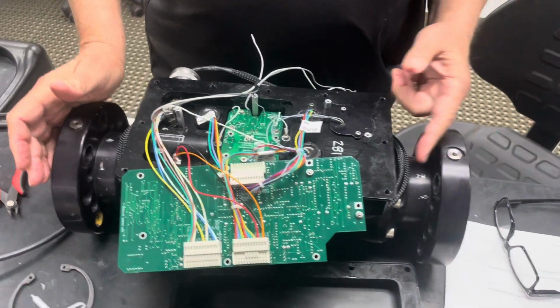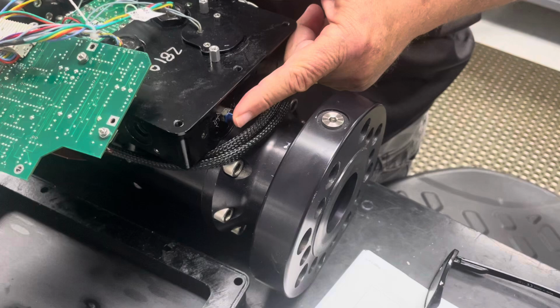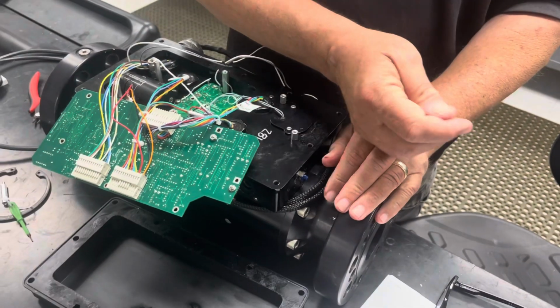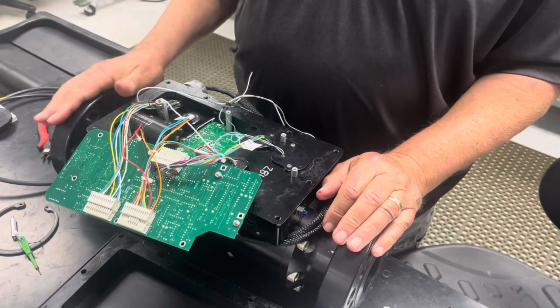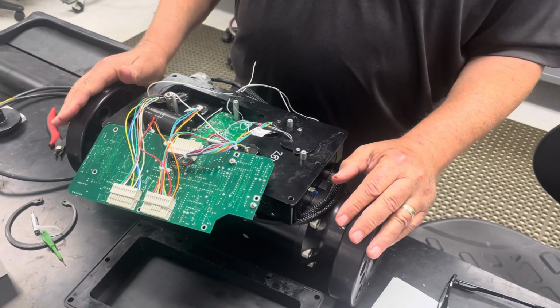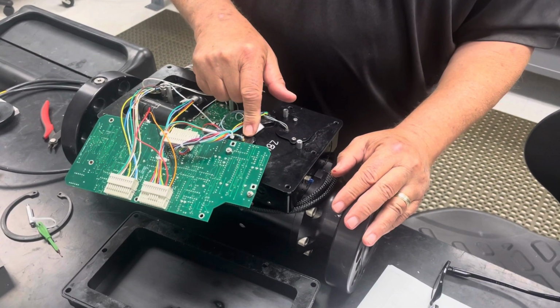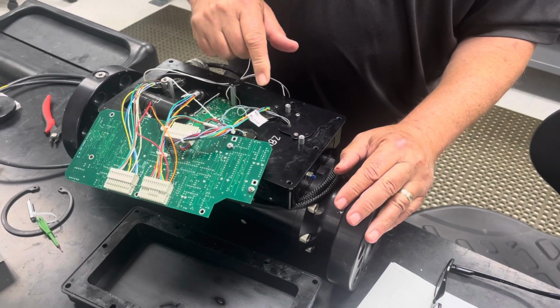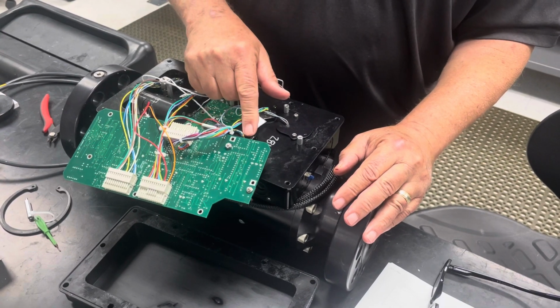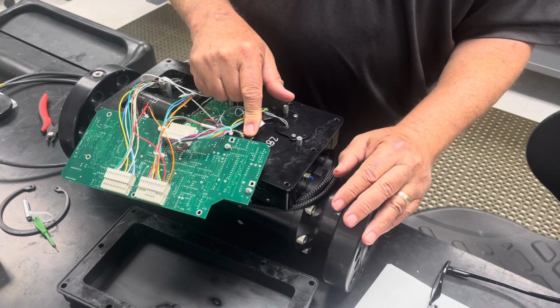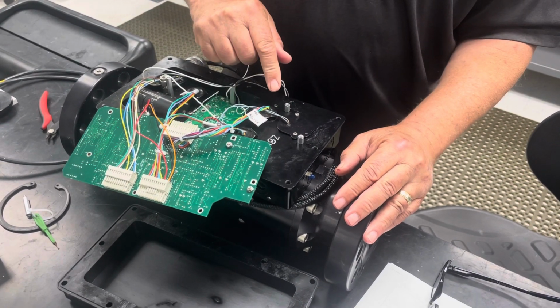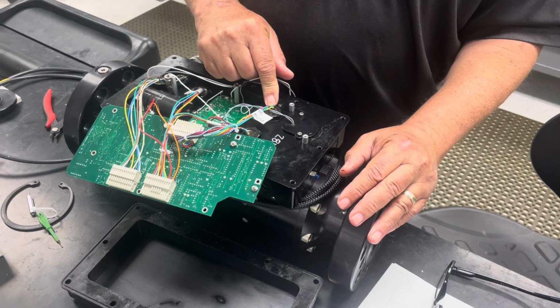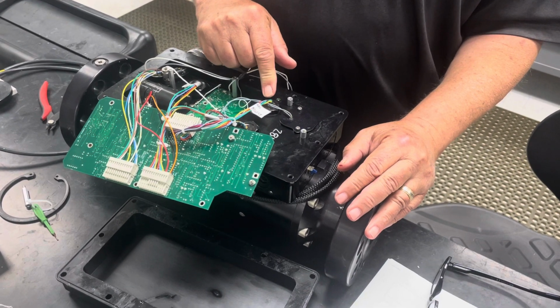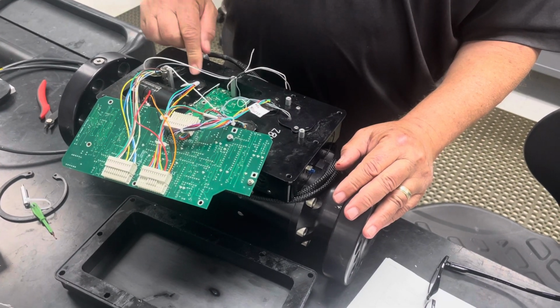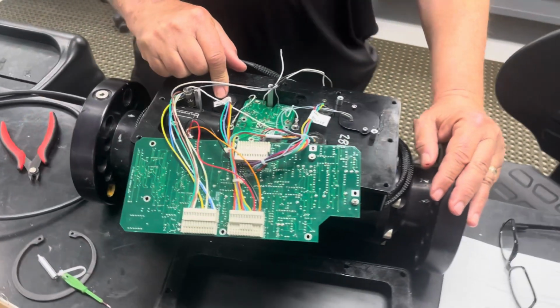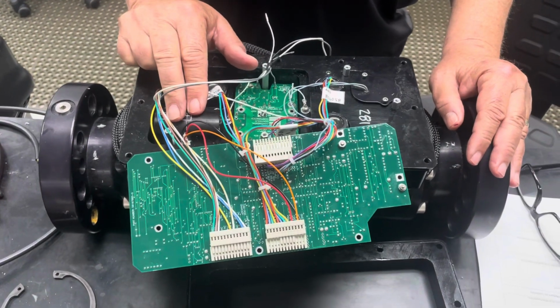Since I got the valve open, here's the regulator here. The valve flows in this direction. So this is the outlet and this is the inlet. This transducer here is the PG transducer. PG is pressure gauge or supply pressure. This transducer here is the PC transducer, so that's the control pressure transducer. This one here is the PO transducer, and this funny looking one is the DP transducer.